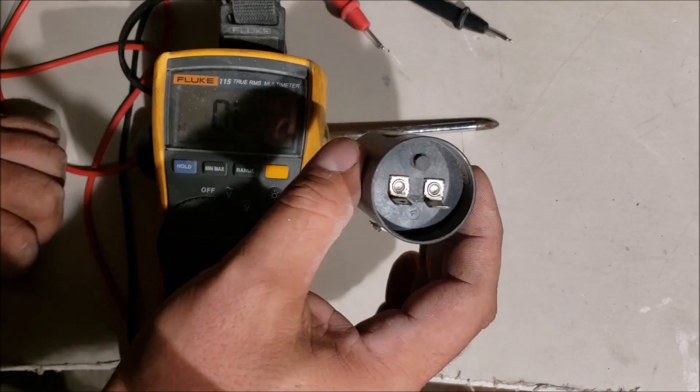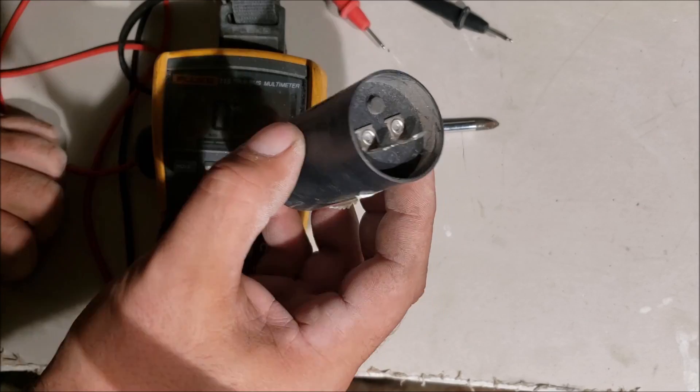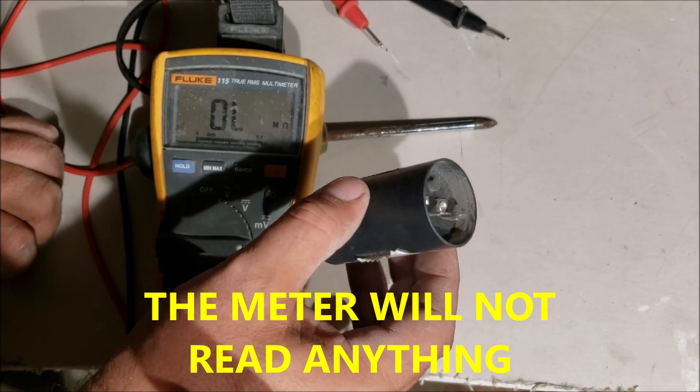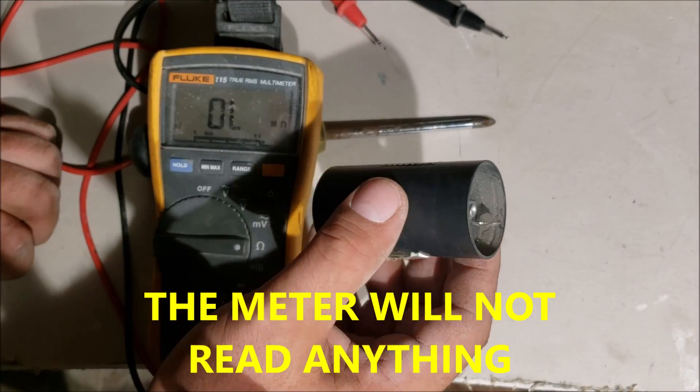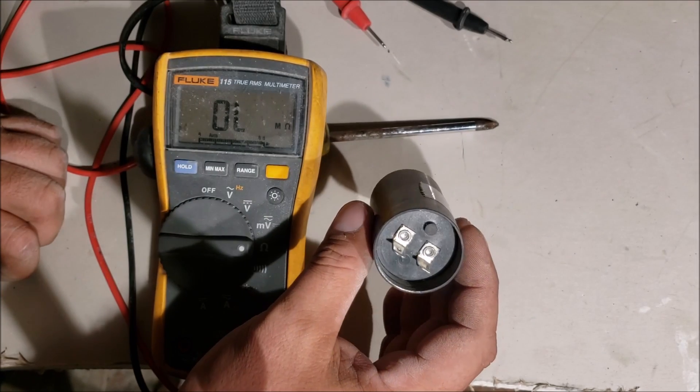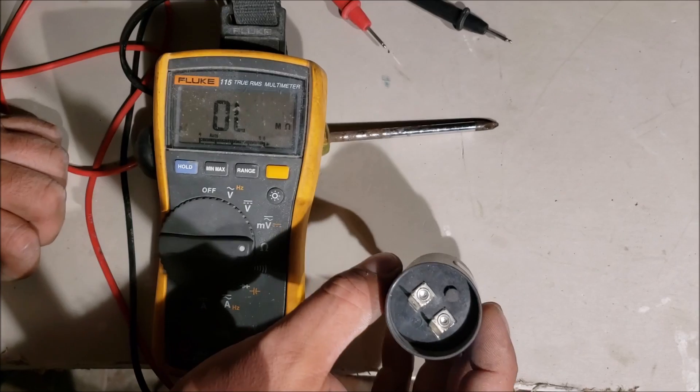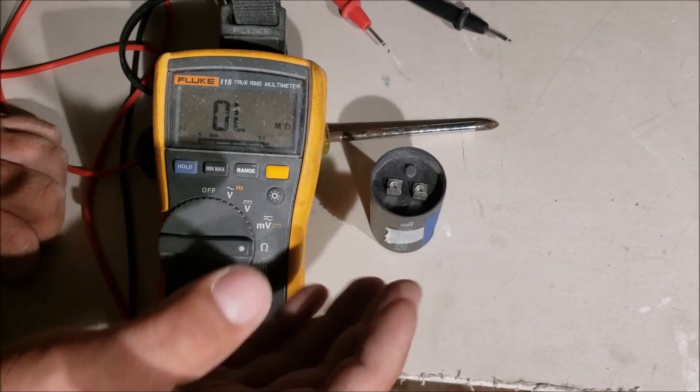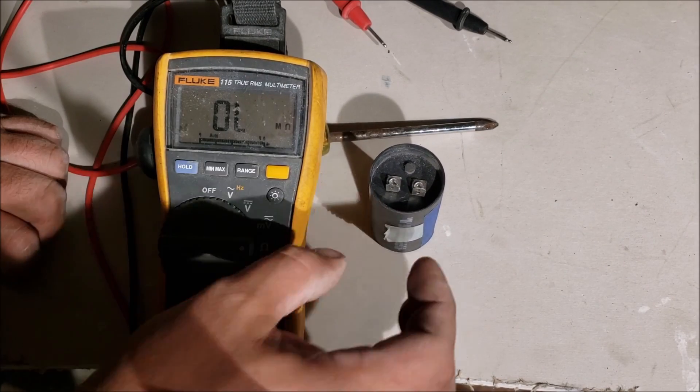This ohm meter test is good to tell if you have a straight up blown one, which happens a lot, but to tell if you have a capacitor that's not reaching full capacity and could be causing start issues, that test does nothing for you. It's still a test that you should see done, but it's only going to give you a dead giveaway if this thing is blown up inside and not working at all.